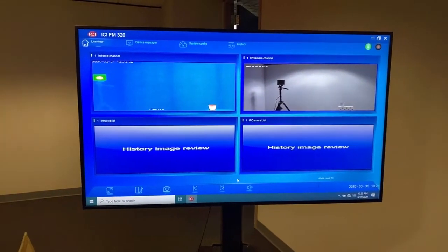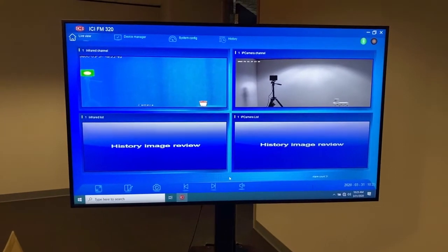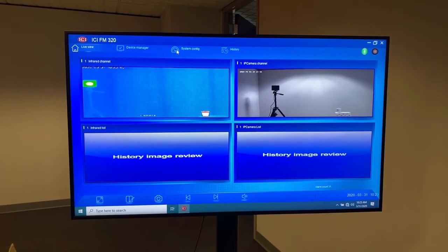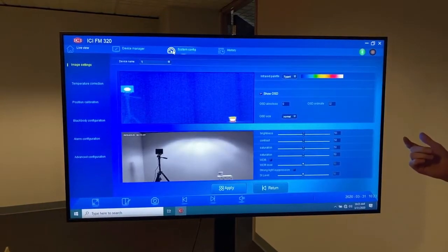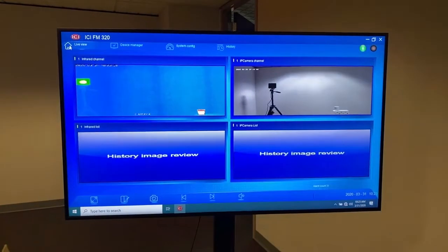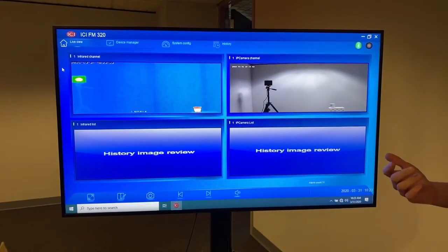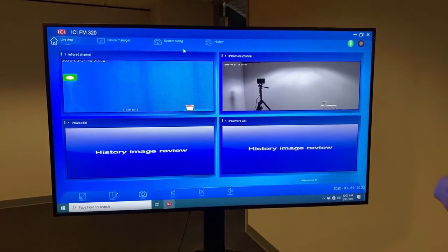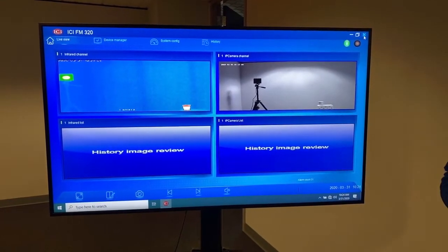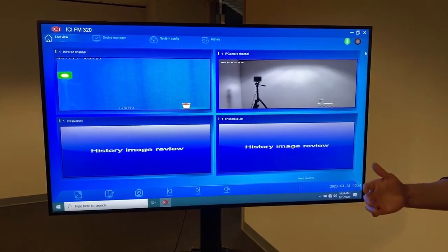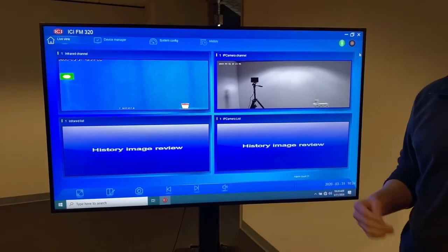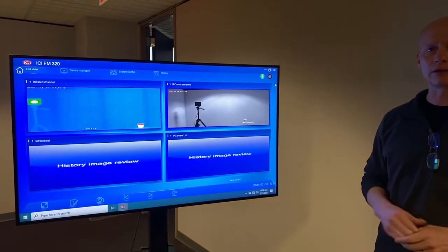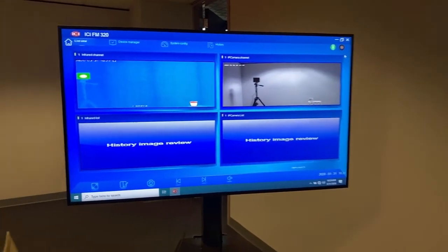We have seen some instances where we've had a frozen video stream. What we recommend, if you're in live view, which is the normal operating mode, is to click off and click system configuration, and then coming back to live view will sometimes recover the frozen video stream. Worst case, if it's a no-joy situation and you can't get any live view, just follow the system lockup procedure. Go through that whole process again of powering down the camera, rebooting the PC, and letting that recycle.